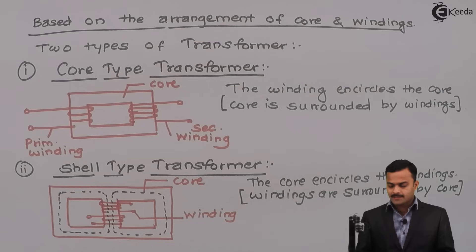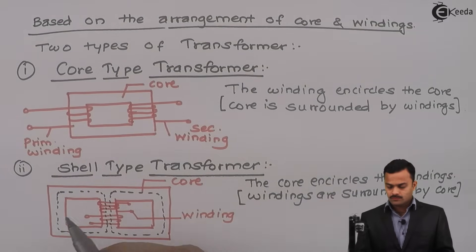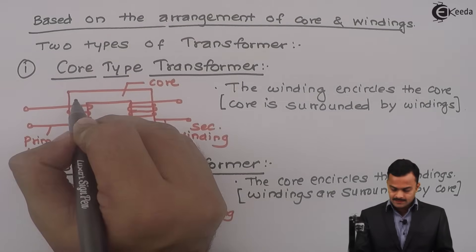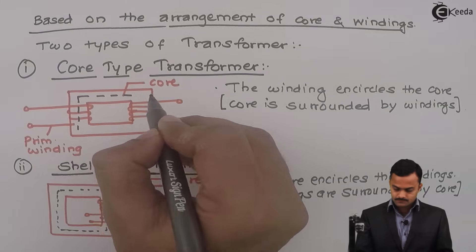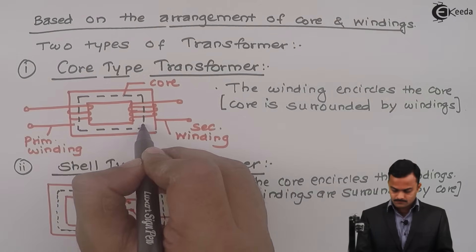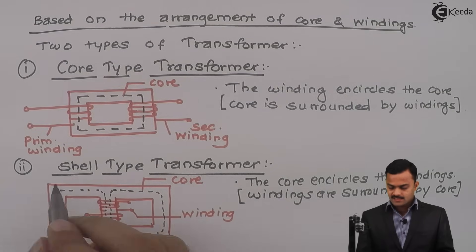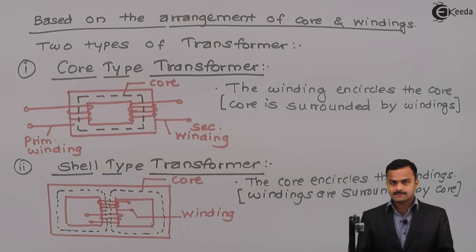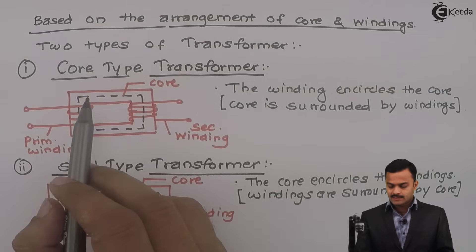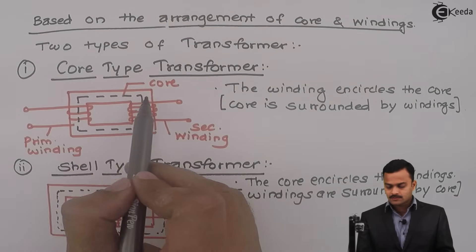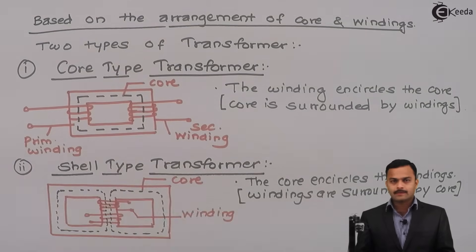So if you see the structure properly, there are some differences between these two. First is obviously based on the construction. Second, this is having only one magnetic circuit, whereas this shell type is having two magnetic circuits. Suppose I want to replace the windings. It is very easy over here. Just take this part of a core outside and take the windings out and replace. But replacing windings over here is not an easy job. So based on the arrangement of core and windings, we have seen two types of transformer. Normally, very high voltage transformers are of shell type. Thank you.